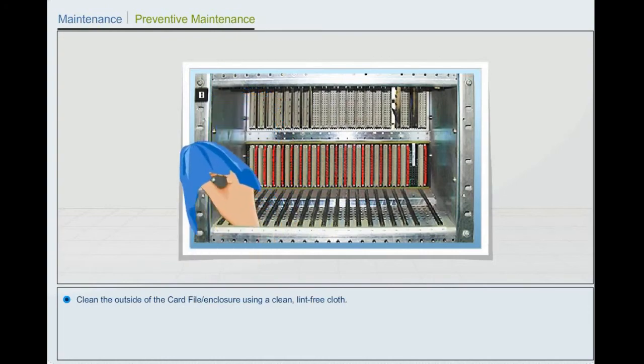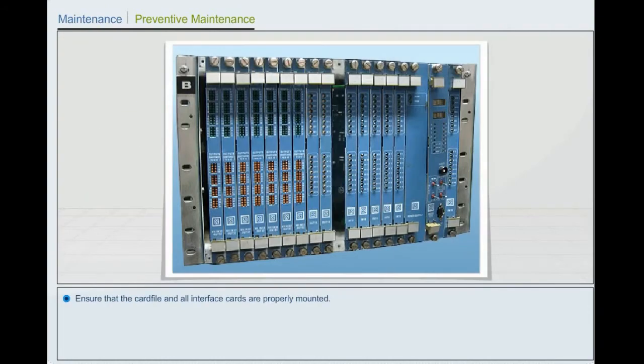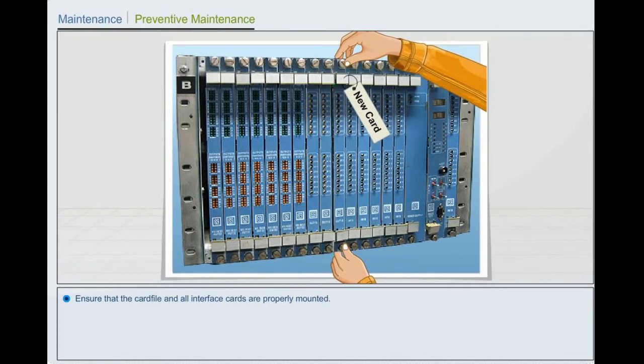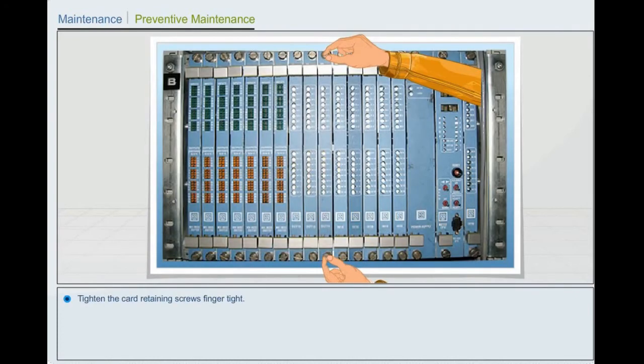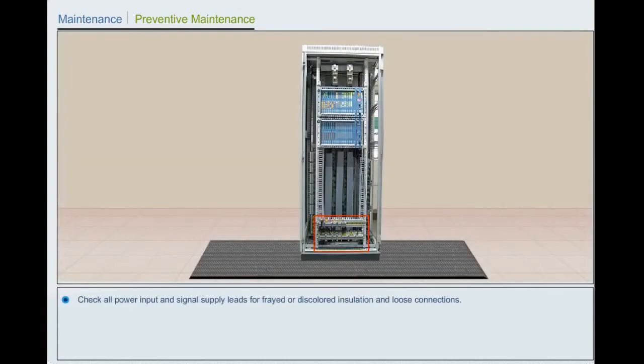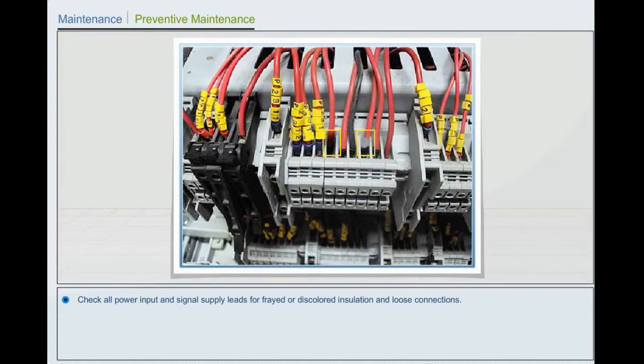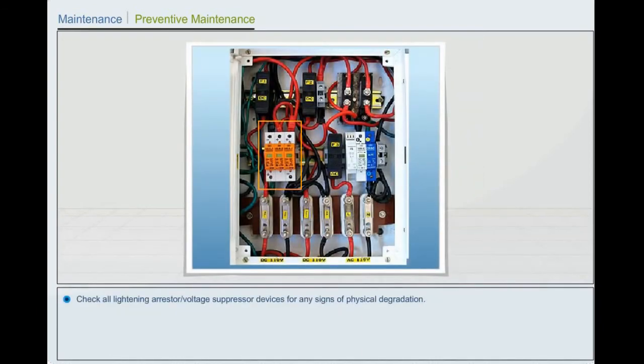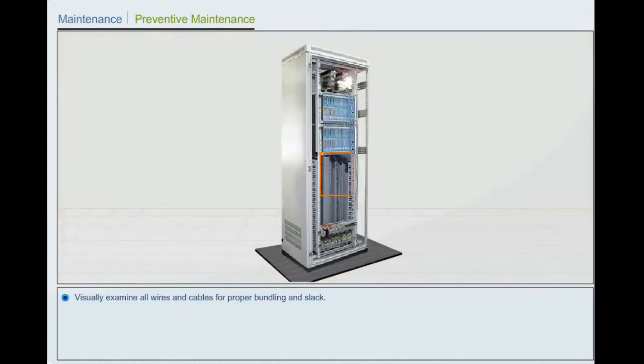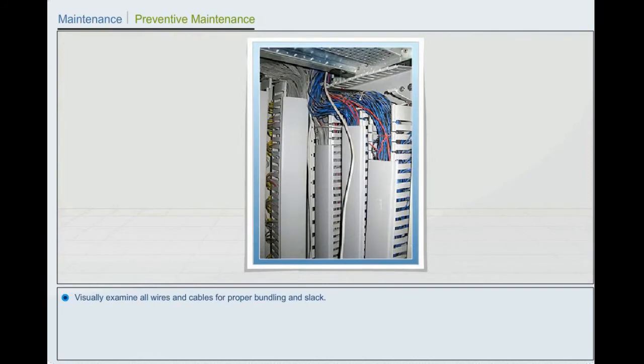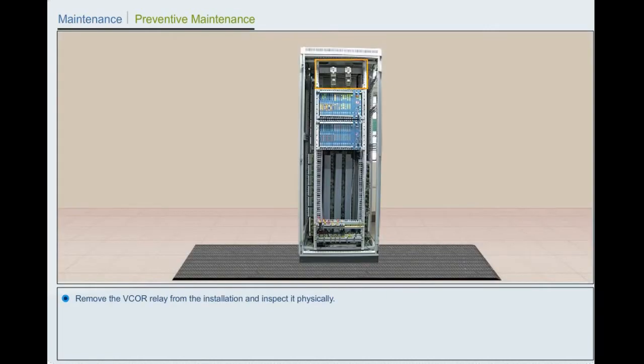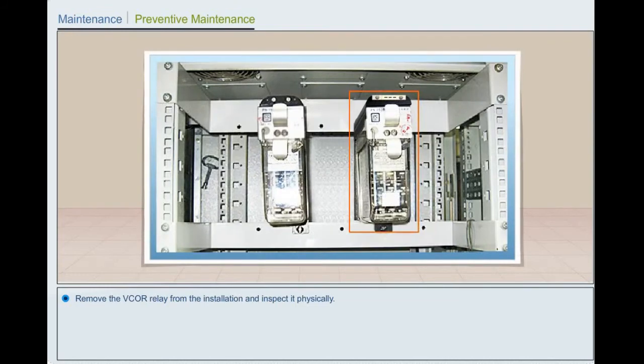Ensure that the card file and all interface cards are properly mounted. Tighten the card retaining screws finger tight. Check all power input and signal supply leads for frayed or discolored insulation and loose connections. Check all lightning arrestor or voltage suppressor devices for any signs of physical degradation. Visually examine all wires and cables for proper bundling and slack. Remove the vital cutoff relay from the installation and inspect it physically.